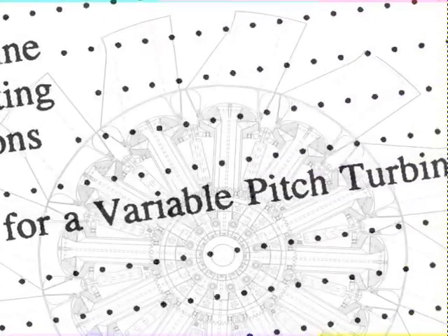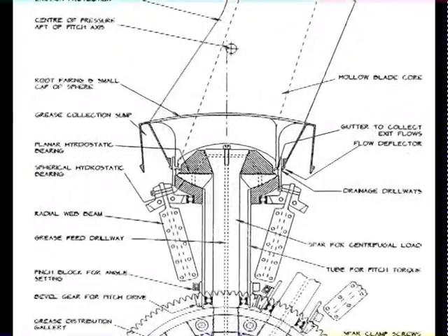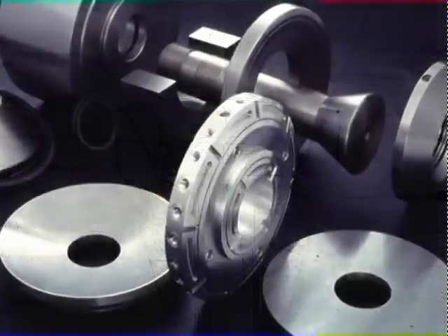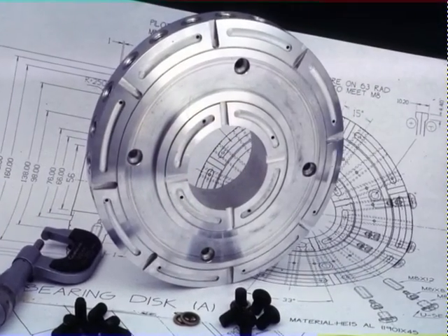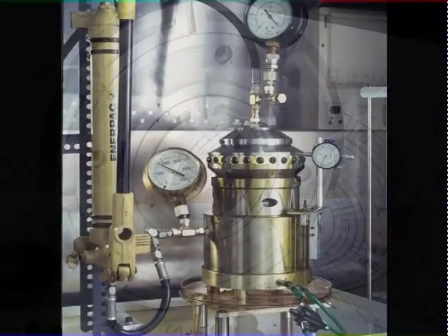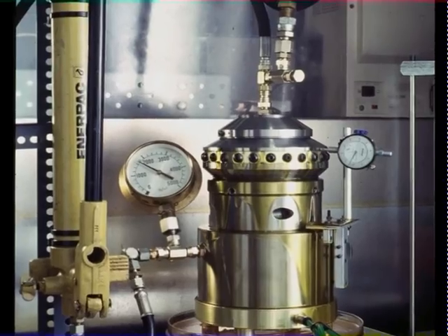In our first study, we thought that the hardest part of variable pitch would be the heavily loaded blade bearings. We built a test rig to try out a planoconvex hydrostatic bearing. After carefully setting flow restrictors for the total of 24 independent pads, the central bearing disc moved freely under a compressive load of 20 tonnes.